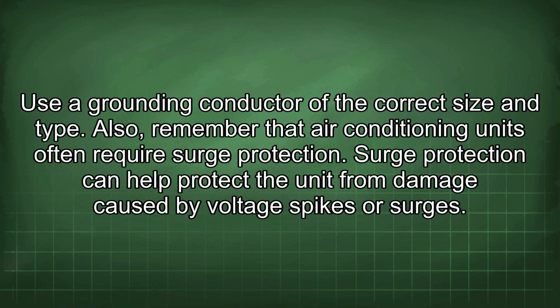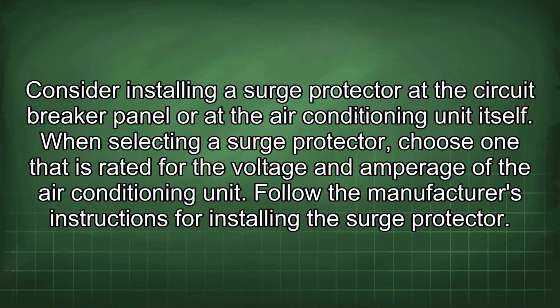Also, remember that air conditioning units often require surge protection. Surge protection can help protect the unit from damage caused by voltage spikes or surges. Consider installing a surge protector at the circuit breaker panel or at the air conditioning unit itself. When selecting a surge protector, choose one that is rated for the voltage and amperage of the air conditioning unit. Follow the manufacturer's instructions for installing the surge protector.